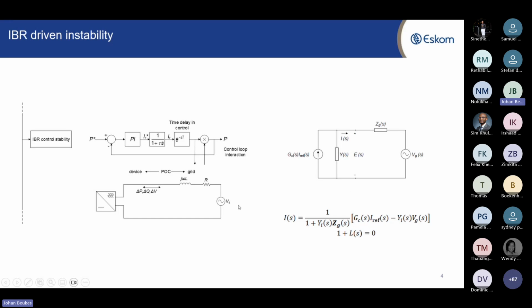So then you look at this equation, and as soon as you get a zero underneath the line, you'll see the influence of a current reference. So in principle, a grid following inverter is a current source, and there's a transfer function, and then these impedances form part of the transfer function. And when that portion below the line, the denominator, becomes zero, then you get instability.